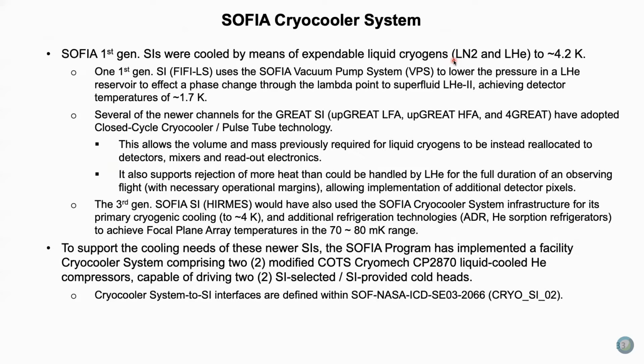So just to give you the history of this, the first generation SIs used expendable liquid cryogens, and actually up to now there's only one SI that did not use expendable liquid cryogen, and that was the GREAT instrument. The first generation SI, like I said, it used this vacuum pump system to pump on a helium bath, got down to 1.7 Kelvin. Several newer channels on the GREAT SI use pulse tubes. And now when it flies, it uses this SOFIA cryocooler system. So third generation SOFIA SI HIRMES would have also used this system.